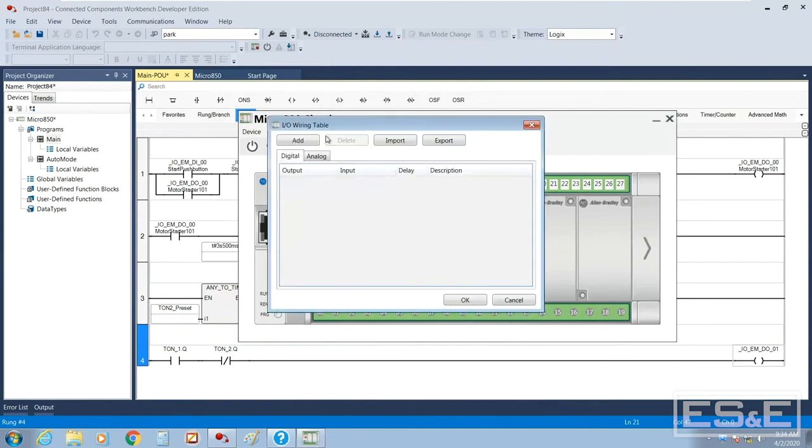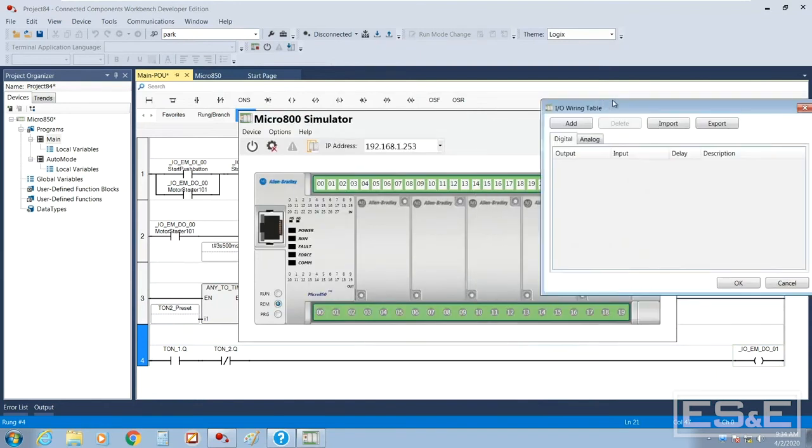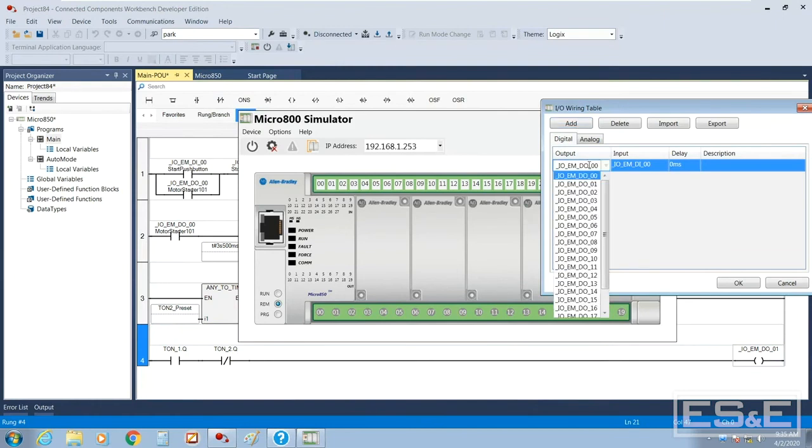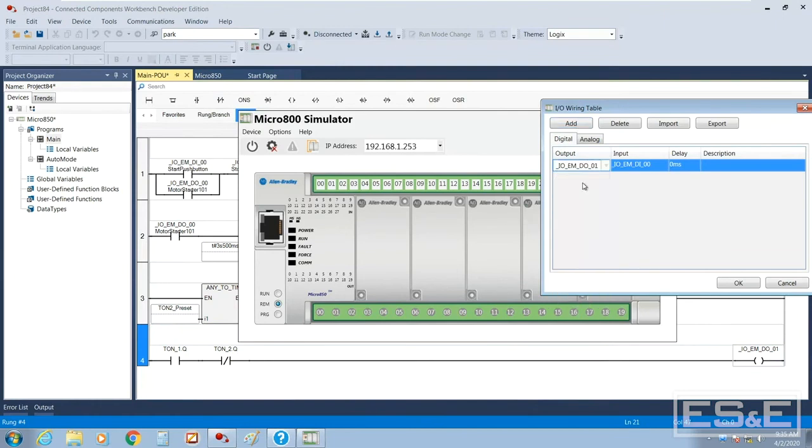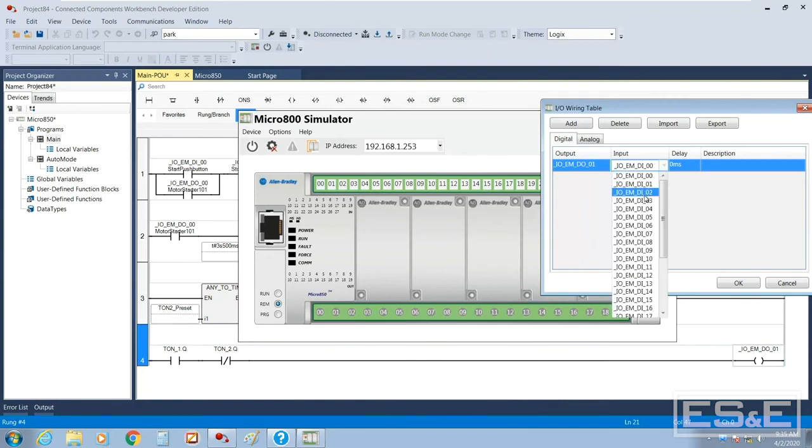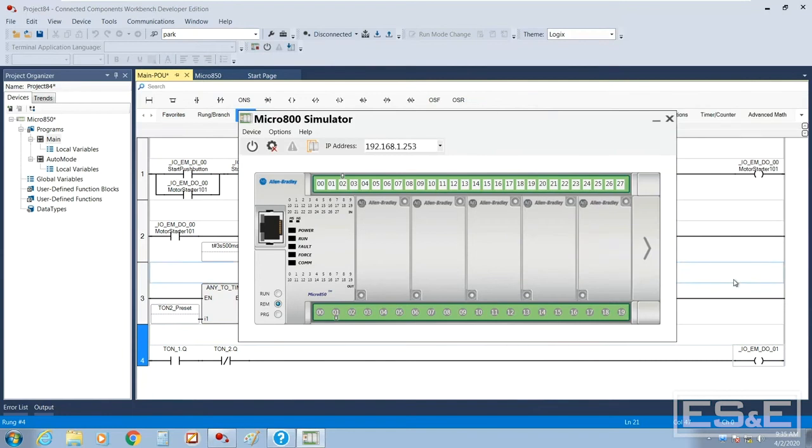So what I'm going to do is show you how you can actually make outputs turn inputs on. This is called a map or wire table. So let's say when output one comes on down here in the logic, I want to be able to turn input two on and I can actually create even a delay right here, which is really cool. So if I want to wait five seconds between the time that this output came on and turn this input on, I can create that delay. So that's our wire mapping.